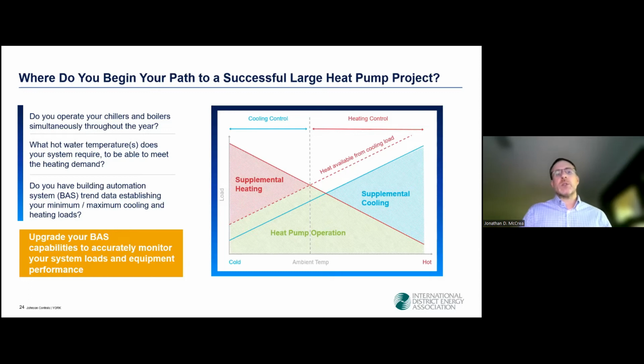Heat pump manufacturers and many consulting firms can help you create a heat pump load model similar to the one on the right of the slide. If you look at the green shaded area at the bottom, that represents the potential simultaneous heating and cooling savings opportunity. And in the upper left, that reddish part is labeled supplemental heating. That's also an opportunity if you have a secondary heat source, where you could use your heat pump capacity to handle the heating load and not have to use supplemental boilers. But we'll talk more about that in session 2.